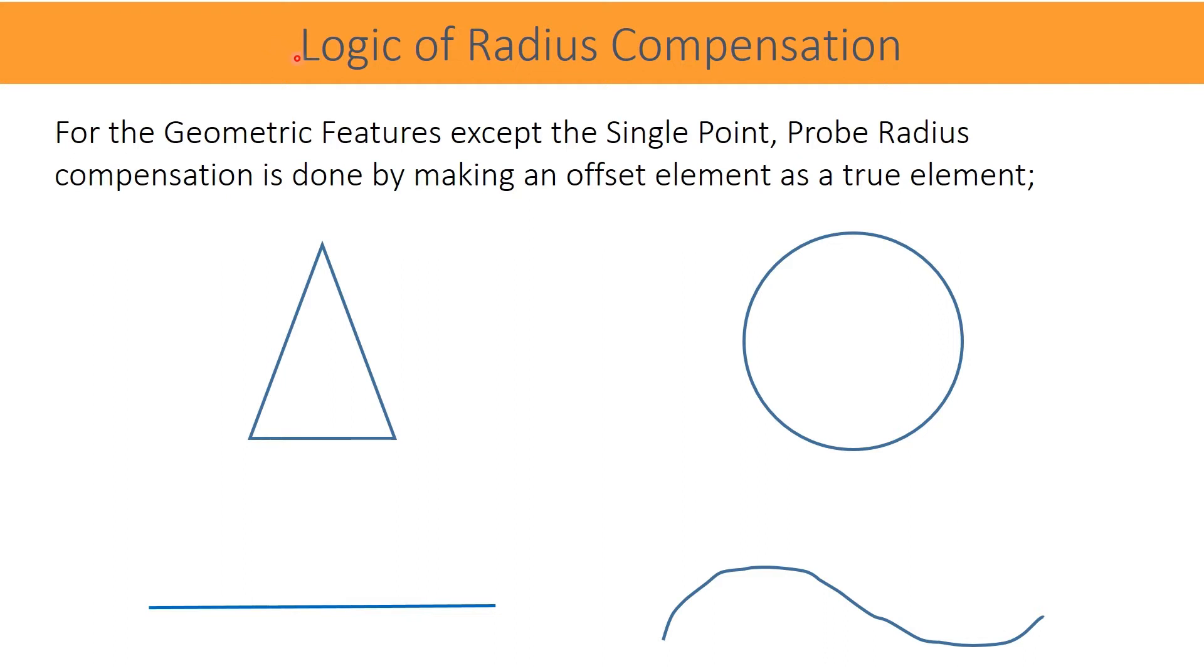Now it is confirmed that point coordinates are transferred from the center of the stylus and radius correction is essential. There are various methods available in the CMM software to correct the radius. The most general and default method is to offset a complete geometry profile. This method runs through software as a default method. In this, a logic used is whether geometry is measured from inside or outside or from below or above.